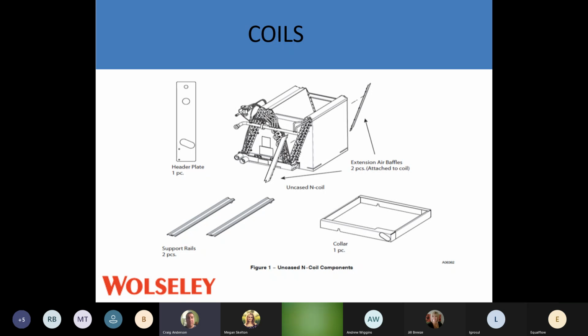And if you do, on the first operation of the unit you're going to run for 15 minutes, you're going to run for 20 minutes, everything's going to look fine, you're packing up your tools and you get out of there. Then you're going to get a call from the customer that the coil is freezing. We're not getting any airflow through that right side. When you take that coil out of the box, it's going to have a metal frame on the bottom of it. You can take that metal frame off, and this is your template.